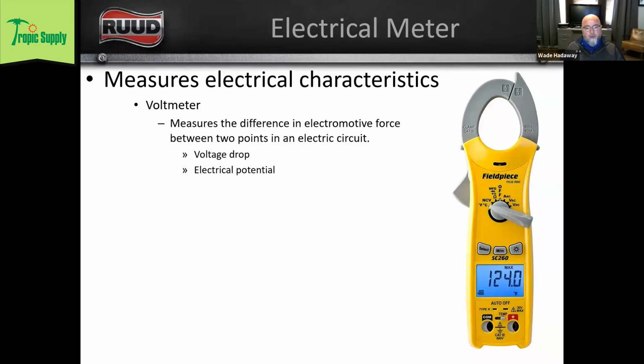So when you're using your meter, you're either checking across a load, an energized contactor coil, a running motor, or you're checking across a switch to see if you have any potential or if you read any voltage drop across a switch. There are a lot of other things that you can use your meter for, but those are the examples we're going to talk about today. And then we have an ammeter, which measures the strength of the magnetic field created by the current.